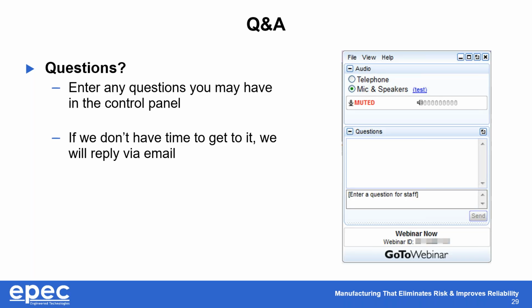And here's another one, the last one I see: do all battery packs need a BMS to control the charging and discharging? The answer is the BMS is mainly for lithium batteries, but we have some nickel metal hydride designs that use a BMS. You have to keep in mind that all lithium battery packs require safety protection as a minimum to be able to pass UN 38.3. So not all battery packs require a BMS, but for lithiums, to manage and get the most out of the life cycles, it's definitely required. And that was the last question I had.